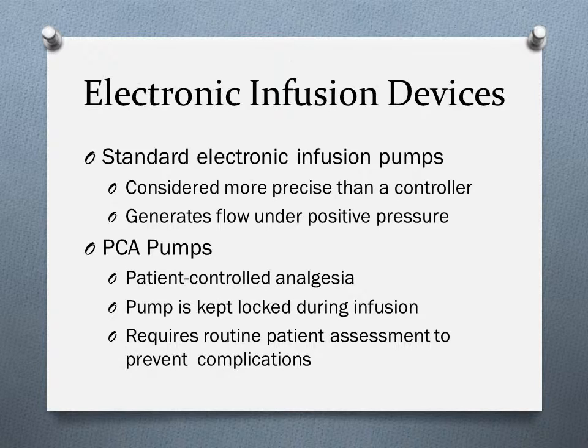General information about the pump: it has a rate range of 1 mL per hour up to 999 mLs per hour, but some specialty models will only go up to 99 mLs per hour and down to 0.1. Other models can deliver up to 2,000 mLs per hour. Usually you can change the infusion in increments of 1 mL, and the accuracy is plus or minus 2%. It has a battery life of about 8 hours. The maximum occlusion pressure will vary with the manufacturer. Usually it's about 4 to 15 psi.